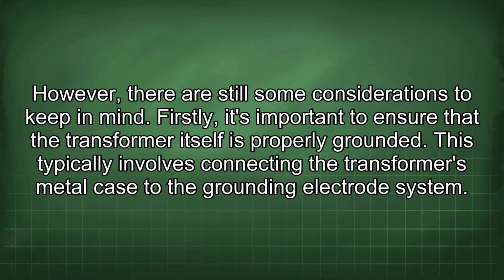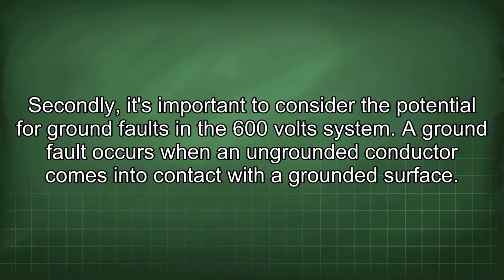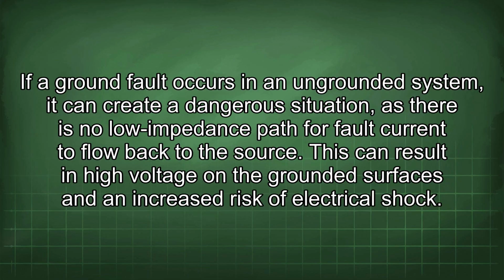Firstly, it's important to ensure that the transformer itself is properly grounded. This typically involves connecting the transformer's metal case to the grounding electrode system. Secondly, it's important to consider the potential for ground faults in the 600-volt system. A ground fault occurs when an ungrounded conductor comes into contact with a grounded surface. If a ground fault occurs in an ungrounded system, it can create a dangerous situation, as there is no low impedance path for fault current to flow back to the source. This can result in high voltage on the grounded surfaces and an increased risk of electrical shock.